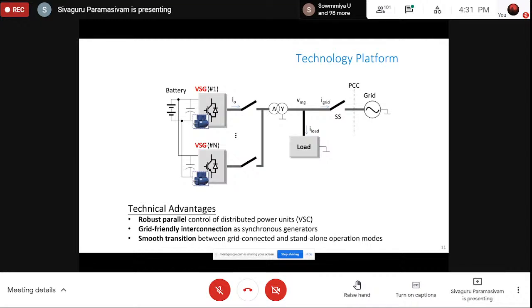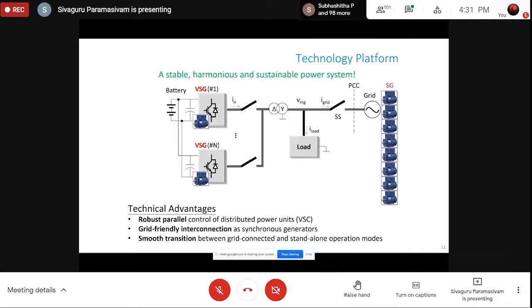When the solar source is higher, we will be able to get high current. When the battery is fully charged, we will be able to utilize the high current. Otherwise the voltage, frequency, phase rotation and everything is undisturbed in the whole system. This is really gaining a great advantage in the global market, particularly in the renewable space. The grid is nothing but a synchronous generator, an actual synchronous generator, right? I'm just implying it, it's not a generator. It doesn't mean the grid has huge generators at the back, but the grid is acting as a synchronous generator.